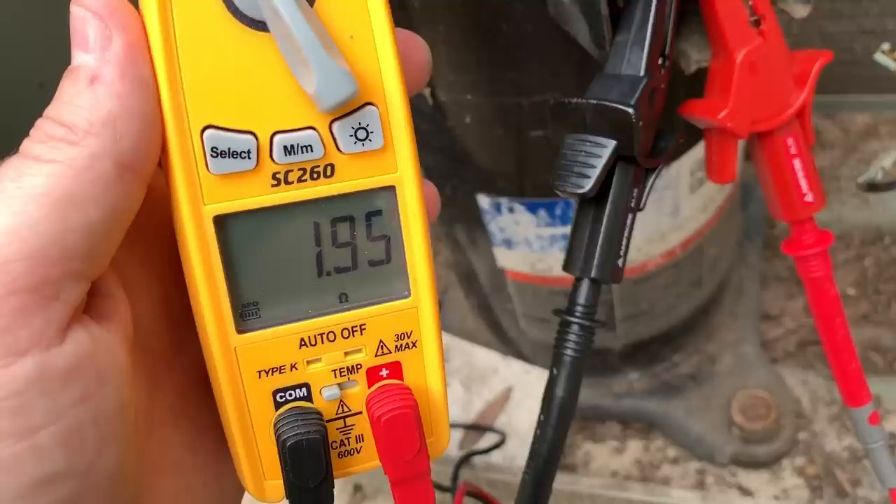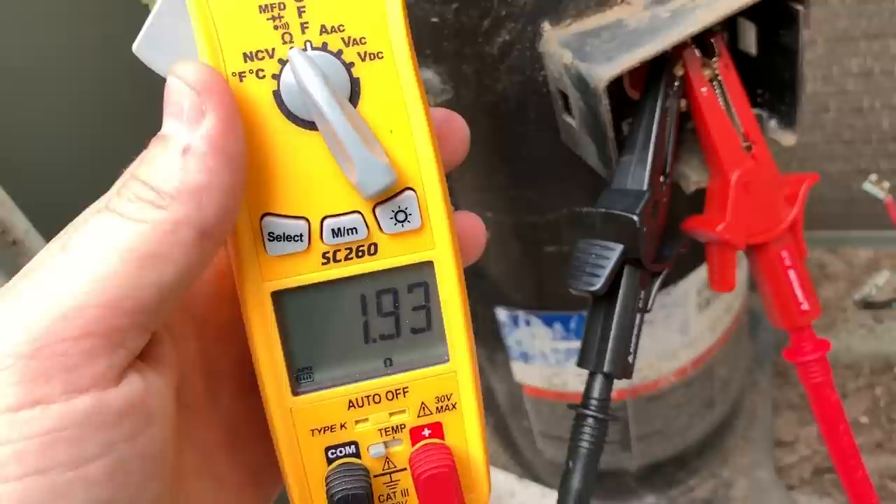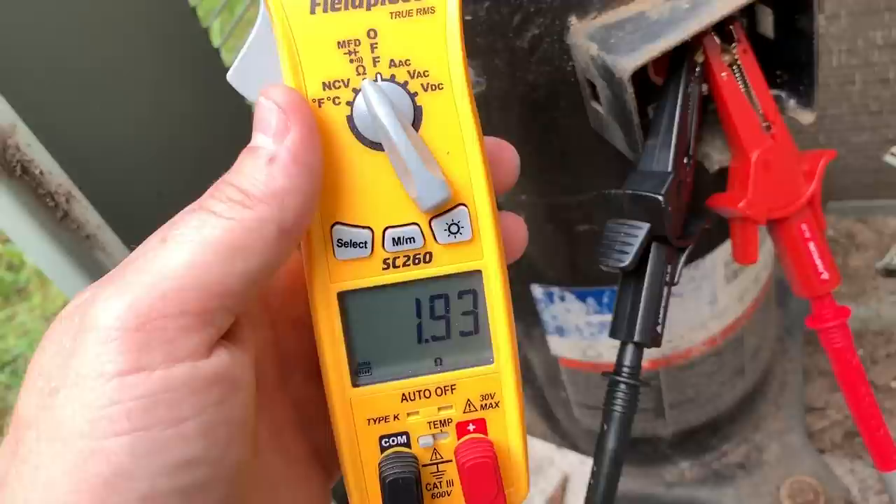Now let's try start. Sure enough, reading 1.95 ohms — so again, in range between start and common. The actual windings themselves are in range. You'd need to look at manufacturer specifications to know what the resistance values on these windings should be, because they vary so much. People who try to give rules of thumb for this just aren't accurate enough.